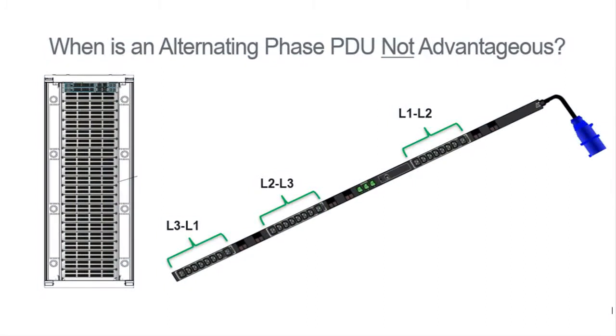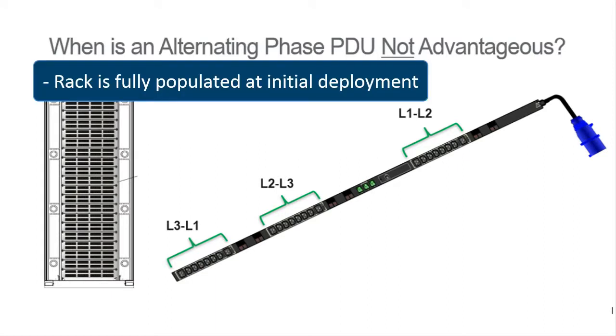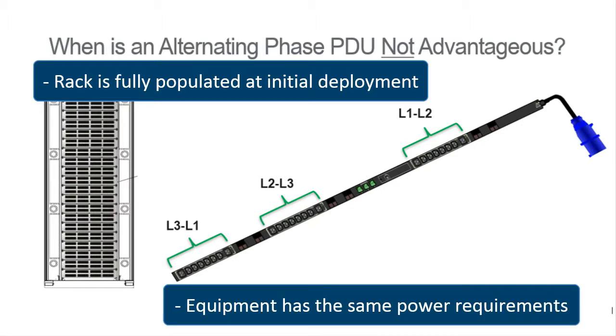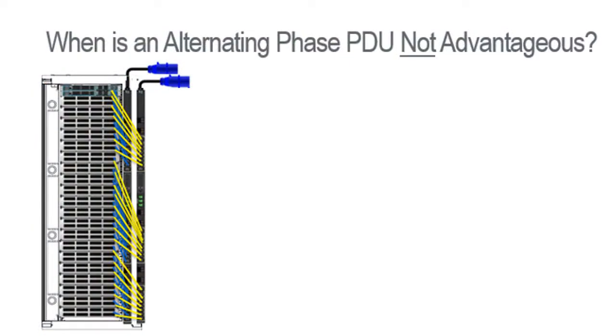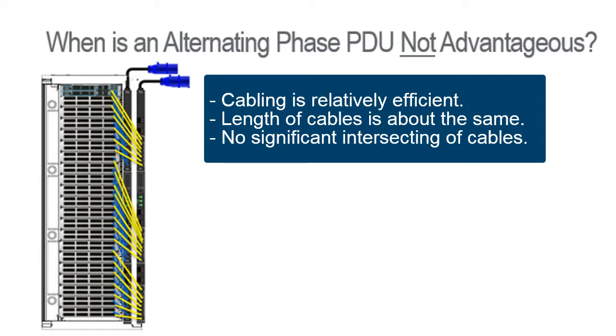Alternating-phase PDUs do cost more, and there's no advantage in paying more if you really don't need this type of PDU. So when don't you need an alternating-phase PDU? For example, if an equipment rack is fully populated at initial deployment and all equipment has equal power requirements, a conventional PDU is probably right for you. With a fully populated rack of similar equipment at initial deployment, the resulting cabling is relatively efficient.